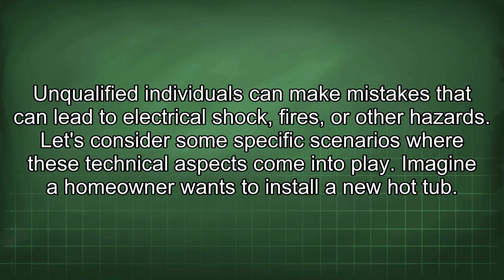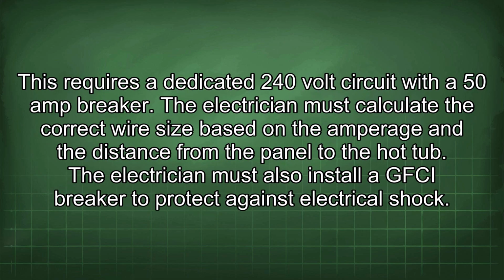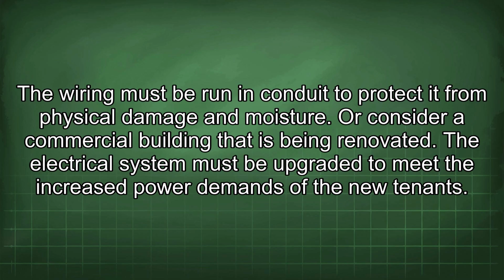Let's consider some specific scenarios where these technical aspects come into play. Imagine a homeowner wants to install a new hot tub. This requires a dedicated 240-volt circuit with a 50-amp breaker. The electrician must calculate the correct wire size based on the amperage and the distance from the panel to the hot tub. The electrician must also install a GFCI breaker to protect against electrical shock. The wiring must be run in conduit to protect it from physical damage and moisture.